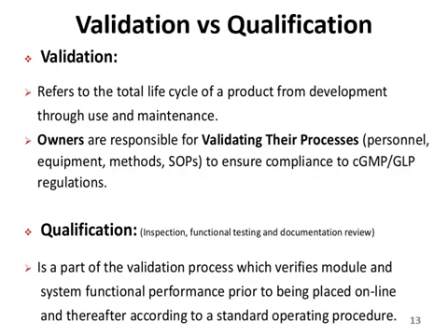Now, the qualification. If you can see, I have written a bit of detail on the qualification. What is included in qualification is the inspection, functional testing, and documentation review. Okay, and if I define it, this is a part of the validation process. Which part of the validation process? I'm repeating, which verifies module and system functional performance prior to being placed online.